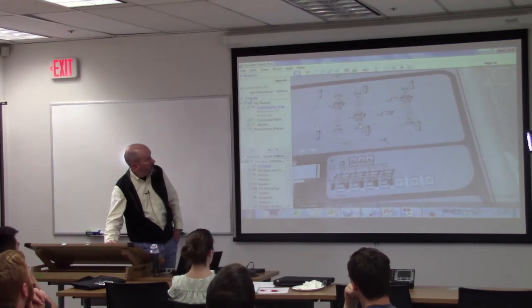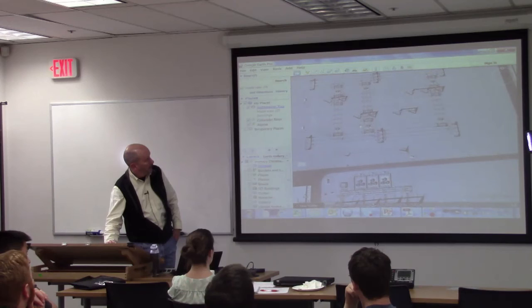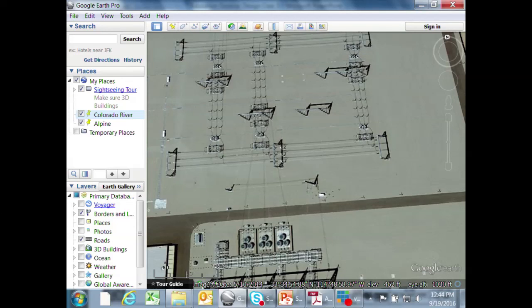Now, the way Edison does their circuit breaker foundations, it's hard to see here, but they just put a big slab down, and then use epoxy anchor bolts to bolt the circuit breaker down to the foundation. It's a lot easier to do it that way. You never have problems getting anchor bolts out of place, and it's also hard in a big slab with a large pattern of anchor bolts to get all 4 of them in the correct location. So this is a method I kind of like and would recommend.